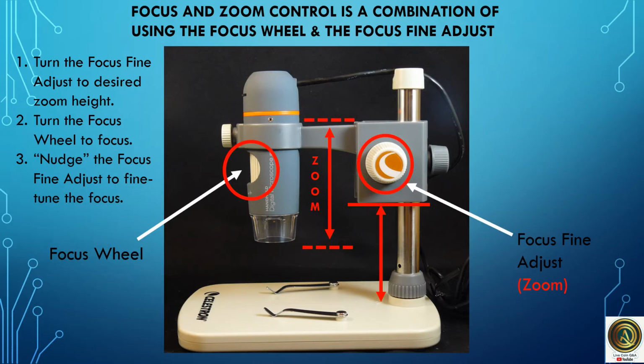Focus and zoom control is a combination of using the focus wheel and the focus fine adjustment knob. First, you turn the focus fine adjustment knob to the desired zoom height. Then you turn the focus wheel to get the item in focus. When it's almost in focus, or as near as you can with this wheel, then you can nudge the focus fine adjustment to fine tune the focus even sharper.